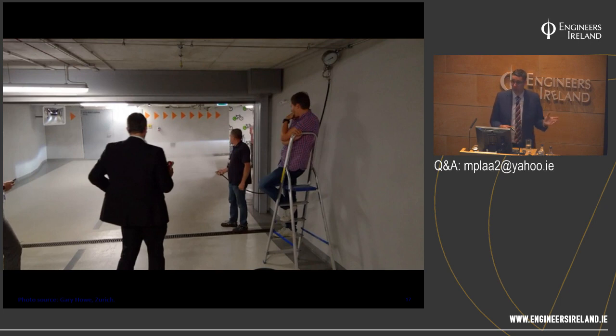And within the sprinkler world, it's generally 60 seconds you're waiting. The worst one I ever had took 14 minutes to get water out of the pipework. I might as well call that a failure, eh?